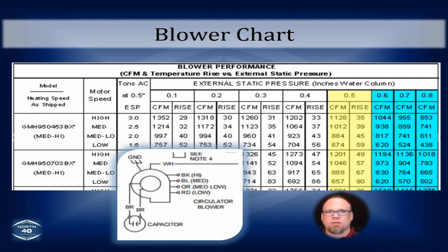Again, here's your blower chart, the blower chart that we just spoke about a second ago. Not a lot of rocket science here. I did want to make sure that we got one more look at it so that everything was crystal clear. Okay, so things you need to look at. You've got your correct model number over on the far left-hand side here. You're on X fan speed, and that X fan speed correlates to your resistance across the top, right? Your static. So that would be the 0.1, 0.2, 0.3, 0.4, 0.5, 0.6, 0.7, 0.8. Okay, that's your measurement before the blower and after the blower, and you add the raw numbers.